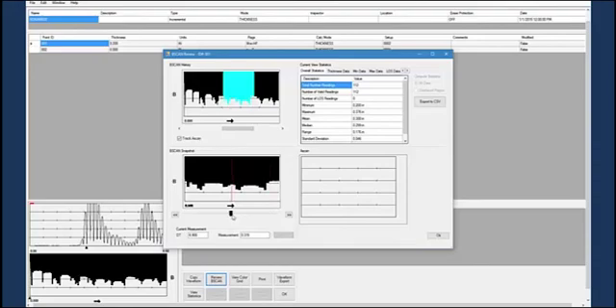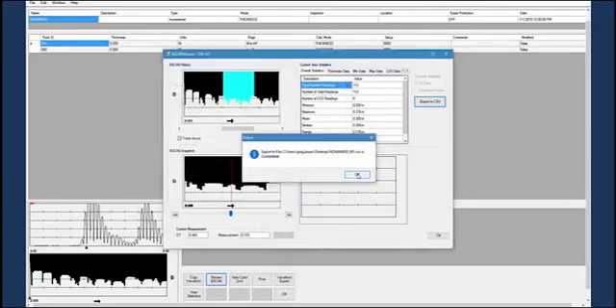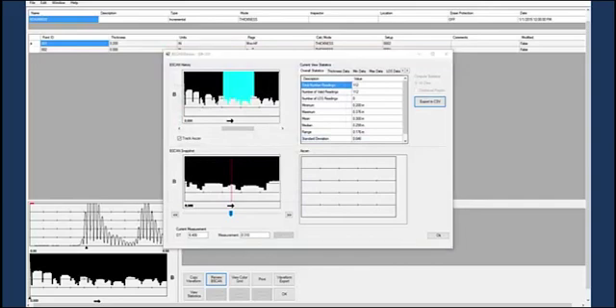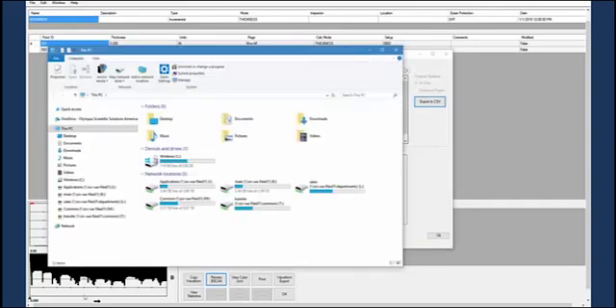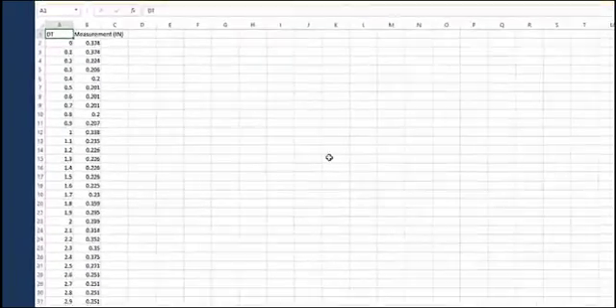The user can also click Export to CSV. The user will then be prompted to choose the location on their computer to save the spreadsheet. Once saved, they can navigate to the file and open it. This will open a spreadsheet with all of the thickness readings and their corresponding distance traveled.